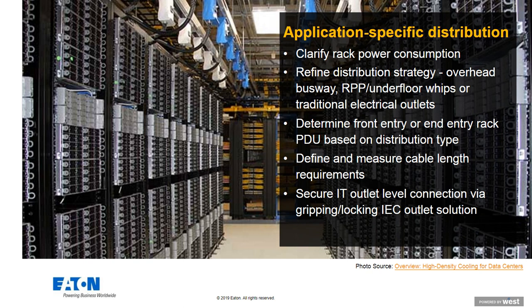The fundamentally first thing you need to do is clarify rack power consumption. A lot of times people refer to that as, what's my kW, the kW of the rack. You'll hear that very often, and that's really just when you add up all the power draw of all the equipment in the rack, what's the kW rating of all the equipment that goes into the rack. And then from there, you can back down to the appropriate type of power, appropriate type of connectors, et cetera.